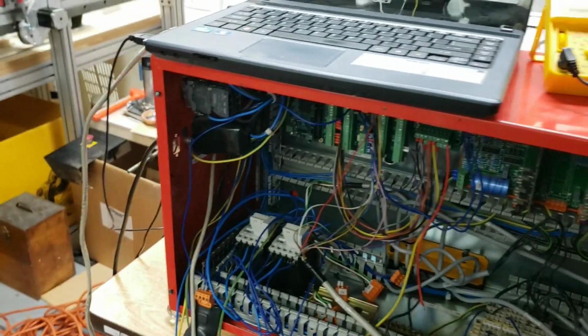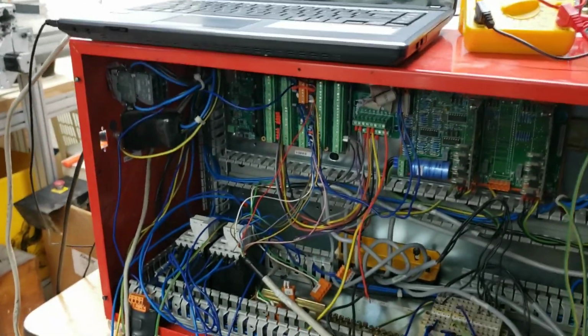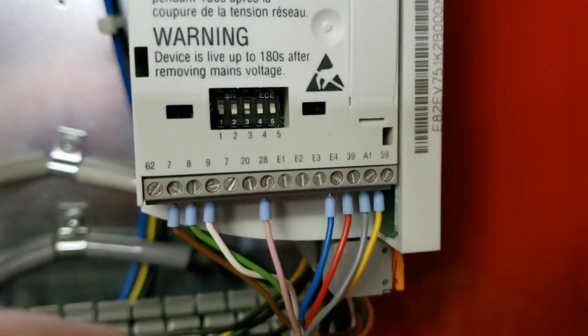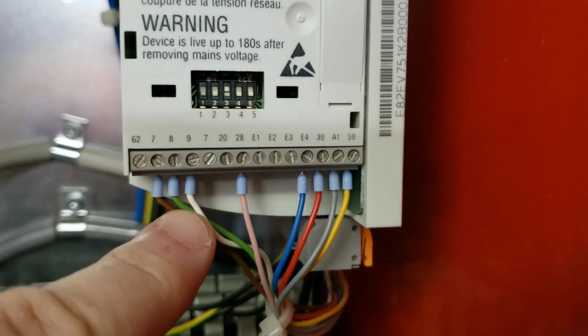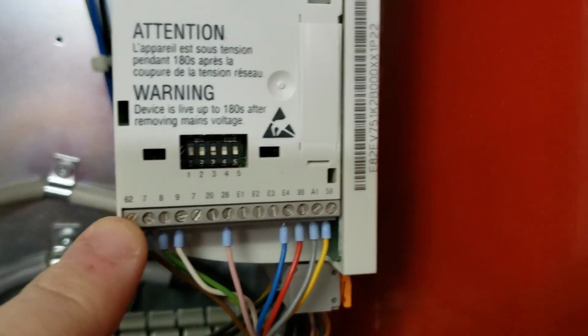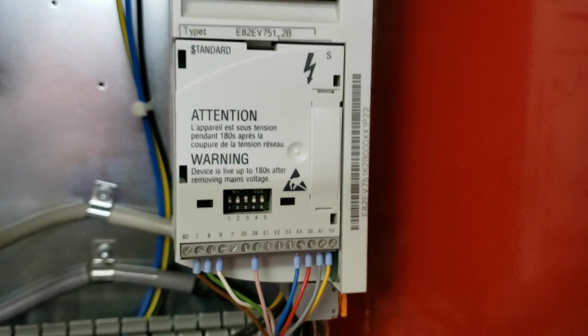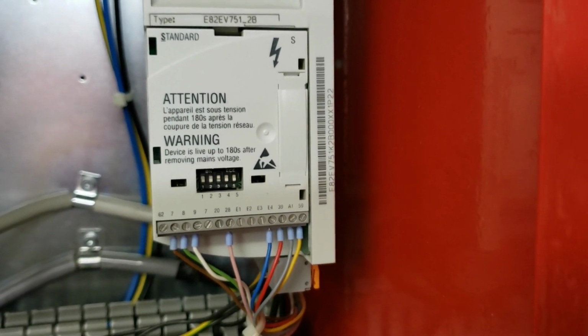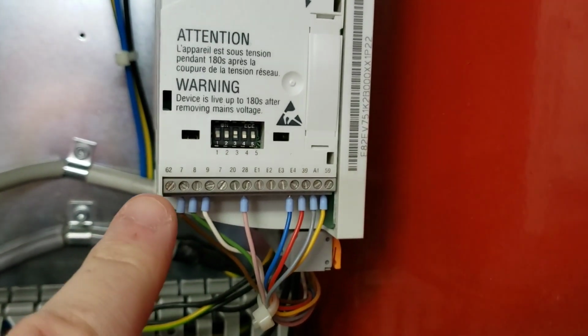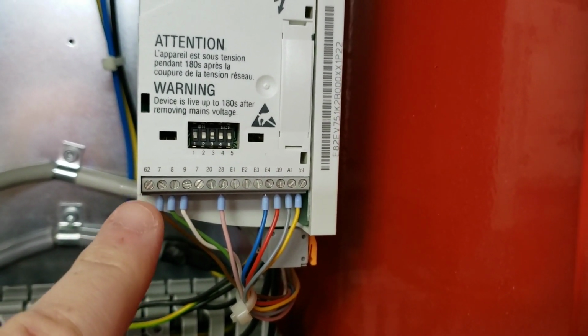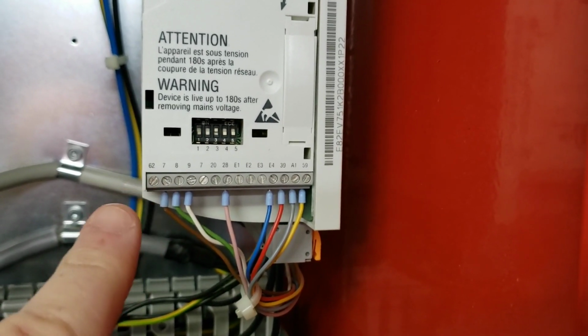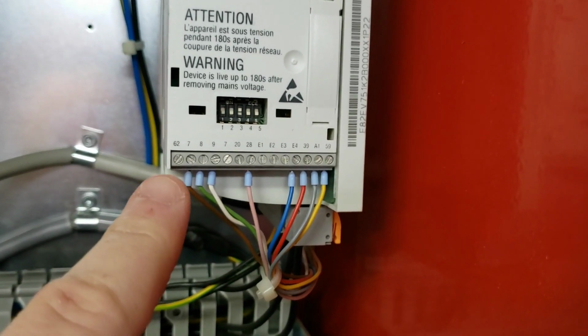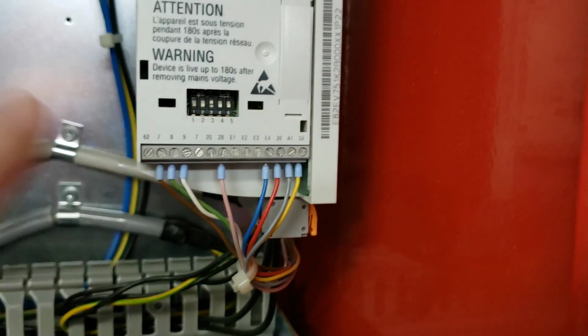But now I have a power switch like a normal person. As far as the VFD is concerned, the way that I have it hooked up right now is a little Frankenstein-y. At this panel here, the original wiring had the white wire in the 62 position, which in the nomenclature they give you says that it is an analog output. I'm thinking that this was an analog voltage output, and it's a variable analog voltage output for some sort of meter. So if you have a meter feedback for your RPM, you can tie it to that lug there.